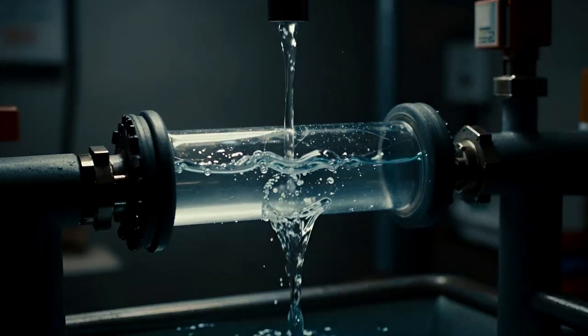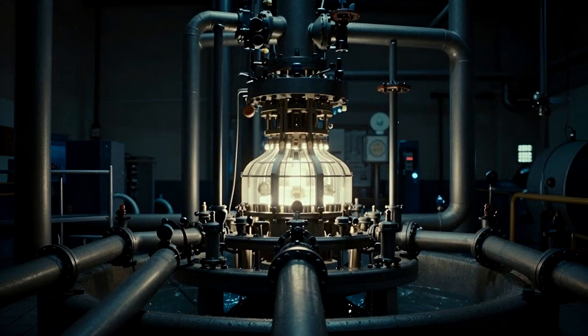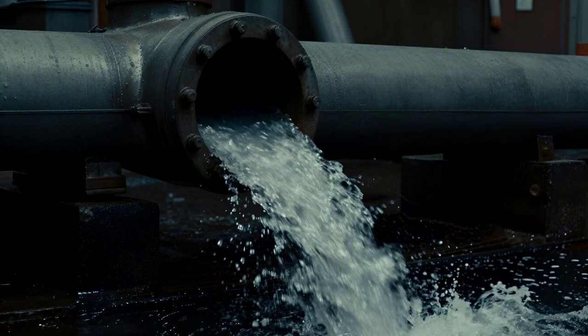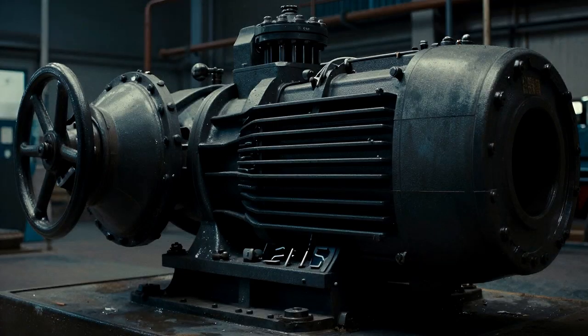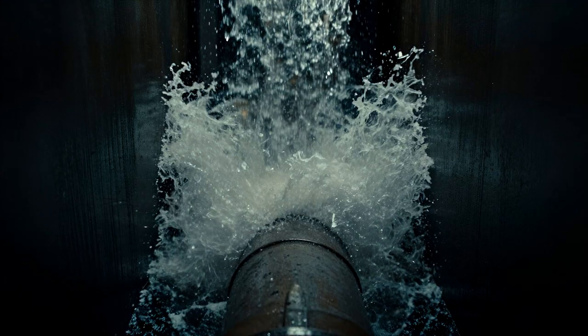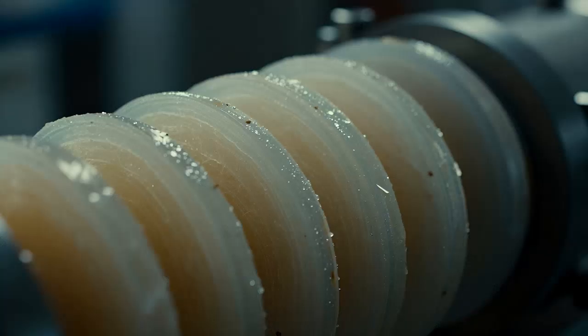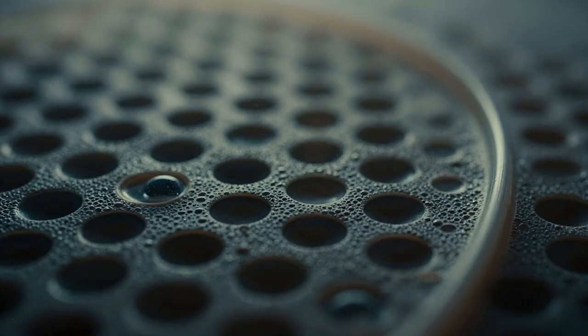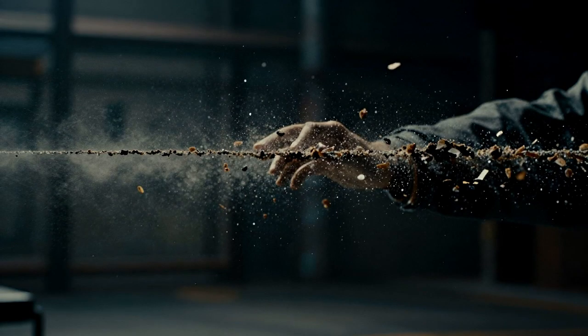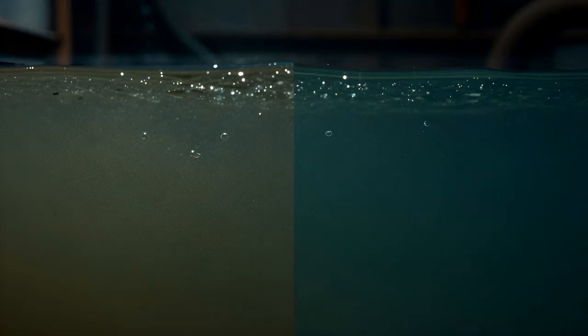Second is reverse osmosis. This is the heart of the purification system and the primary culprit for the massive volumetric water loss. High-pressure industrial pumps violently force the pre-treated water through semi-permeable membranes, featuring microscopic pores measuring approximately 0.0001 microns. These membranes successfully reject 95% to 99% of all dissolved solids.